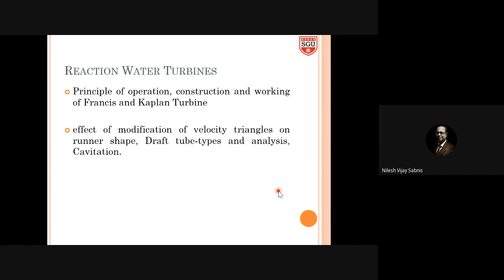In general, nearby dams like Radhanagari or Chandoli Dam are using such types of reaction turbines, because as compared to the Koyna Dam project, the head available is less, and that head is also not constant. For that, the reaction turbine is the best solution, which requires low head, and we can keep high discharge by maintaining a large diameter of the wheel.